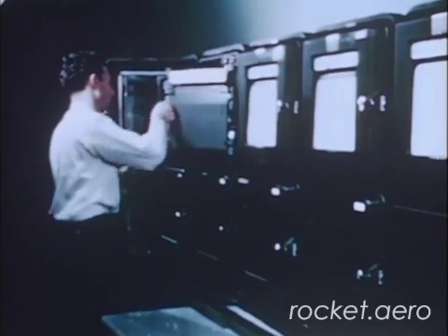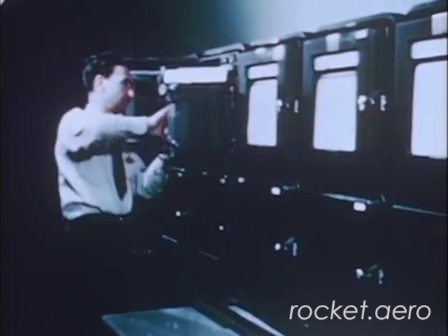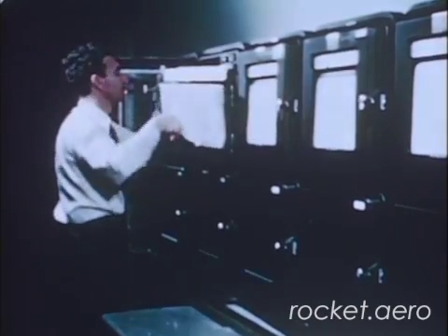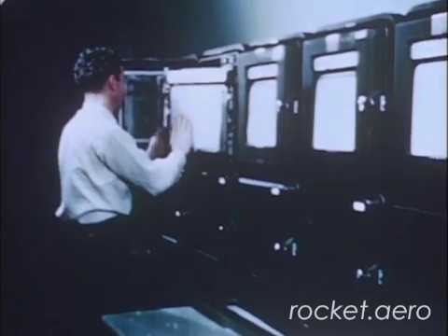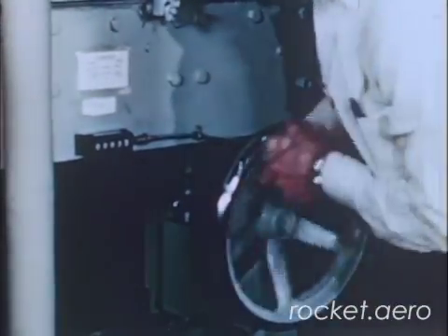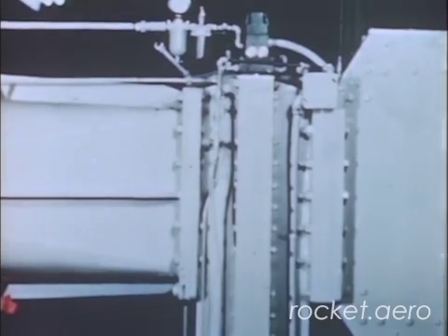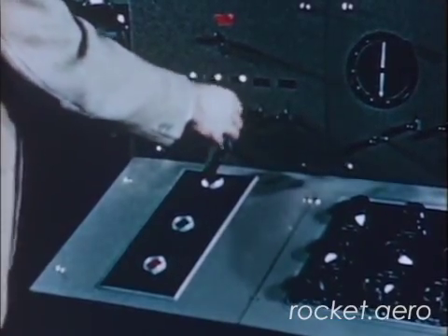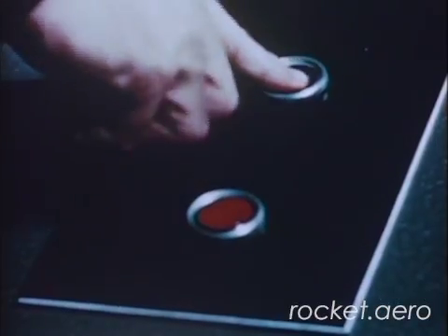After the dry air storage chamber is filled and the vacuum chamber is evacuated, final preparations are made for a run. The engineer loads the SpeedoMax recorders, the Schlieren optical system is prepared and the camera is focused, and the plates of the variable diffuser are set to the calculated level. The vacuum chamber gate valve, which starts and stops the airstream, is ready for action. Just before starting, the engineer checks all components of the tunnel and then presses a button which opens the gate valve.